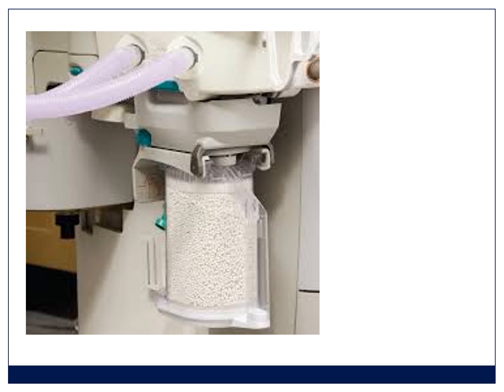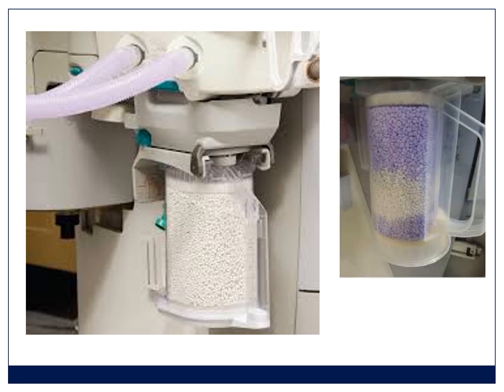There should ideally be less than 50% color change at the start of an anesthetic, which tells you about absorber saturation. Now, you can actually use these for longer than that, but you need to be very confident that you can change soda lime in the middle of a case. Remember that you can do it. It seals off the circuit, but if you're not sure, rather just change the soda lime. When it starts to get used, it changes color to purple, like that.